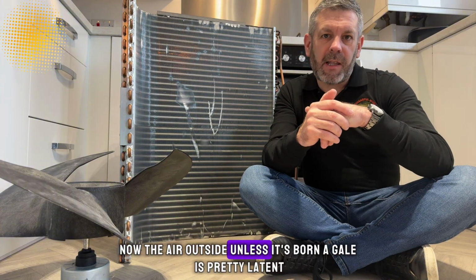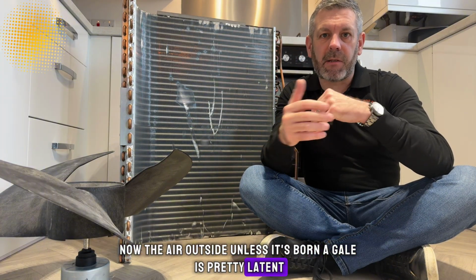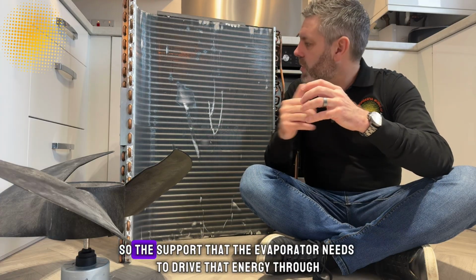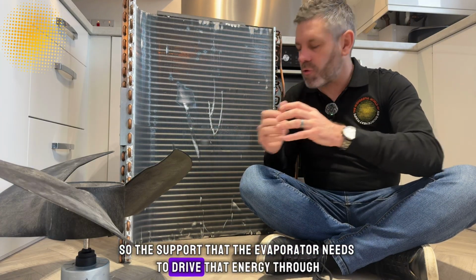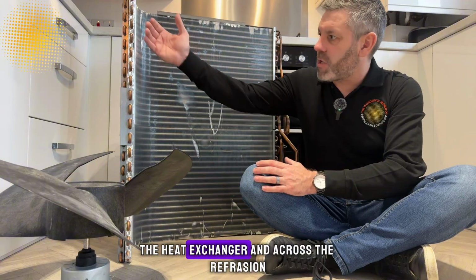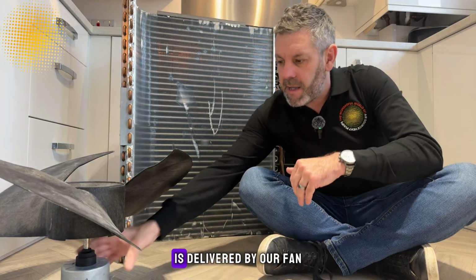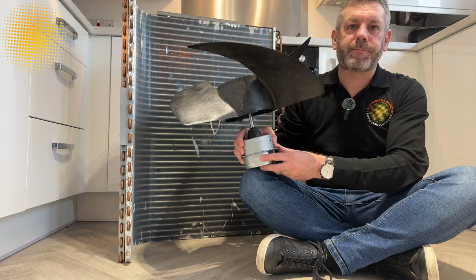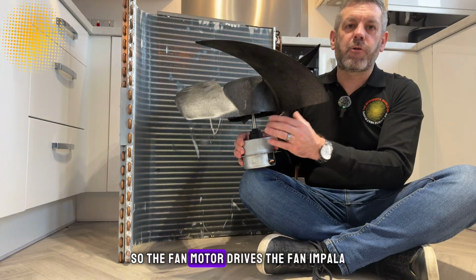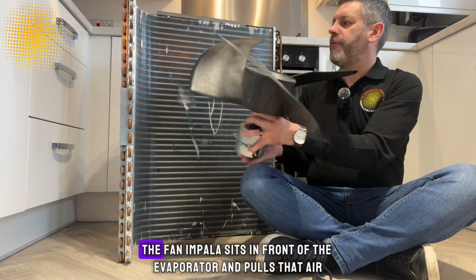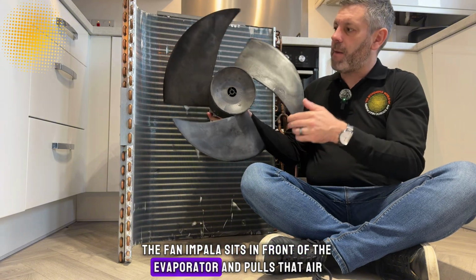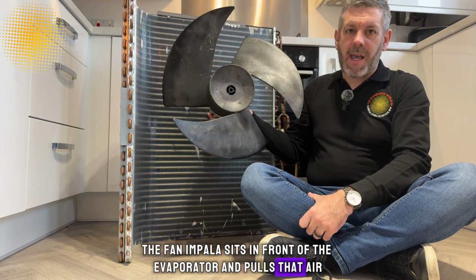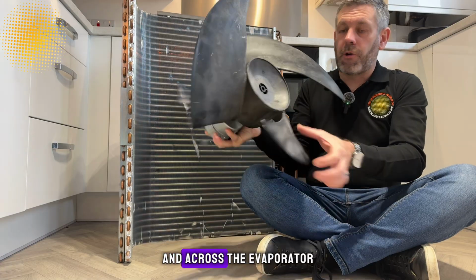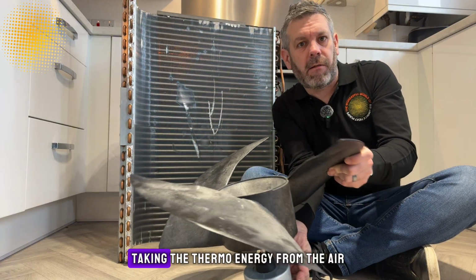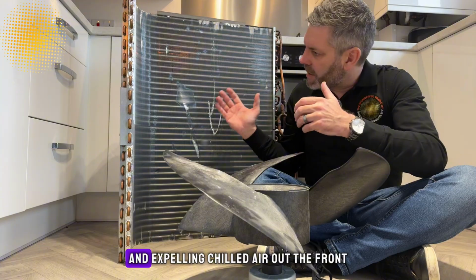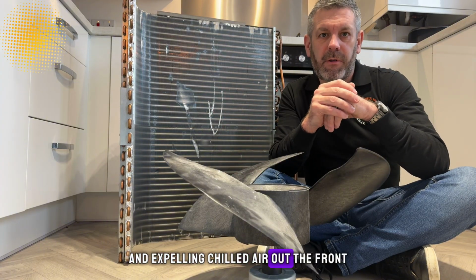Now, the air outside, unless it's blowing a gale, is pretty latent. There's not a lot of movement. So the support that the evaporator needs to drive that energy through the heat exchanger and across the refrigerant is delivered by our fan. The fan motor drives the fan impeller. The fan impeller sits in front of the evaporator and pulls that air in across the evaporator, taking the thermal energy from the air and expelling chilled air out the front.